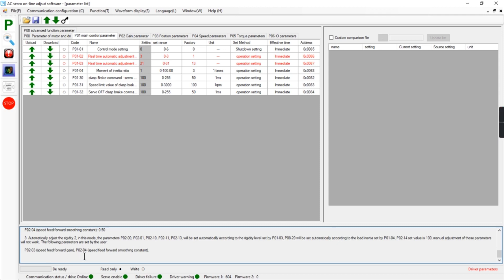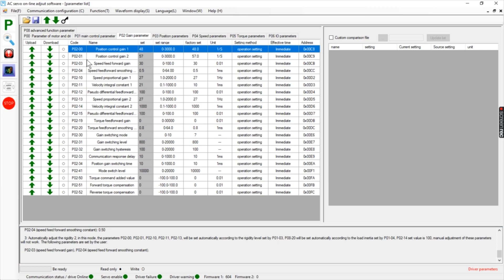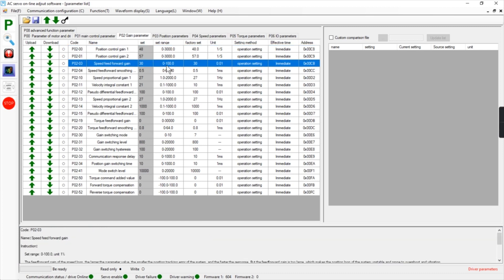That's parameter P02-03 — speed feed forward gain — which we can set from 0 to 100. I'm at 30 right now. Let's set that to 50 and upload it.